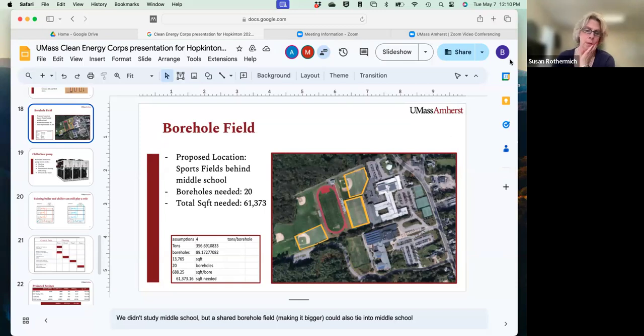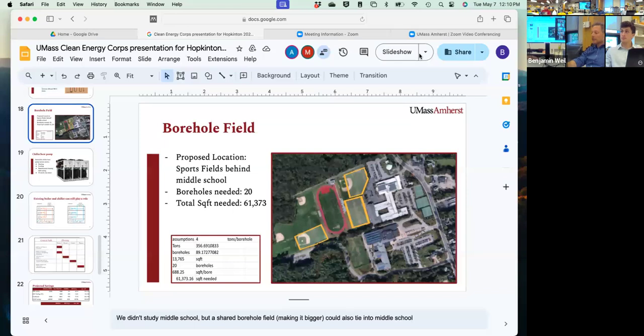So the middle school, Tim, correct me if I'm wrong, we have two boilers and we just replaced them in the last couple of years? Three, yeah. So we got rid of two pressure vessel boilers and replaced them with three condensing boilers. So that's even better. So now you've got high efficiency boilers, and you've got these really excellent boilers in the high school, even though they're not condensing, they're excellent quality, right? So you have the backup capacity.